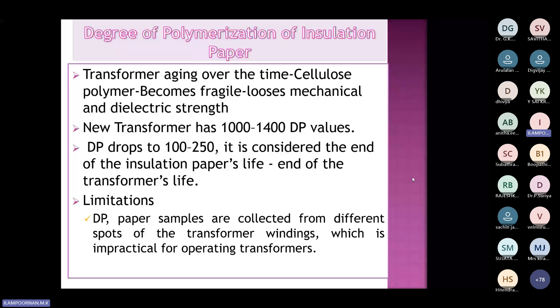That is the worst case, and it won't happen for 100 years - maybe another 100 or 200 years, we don't know. So if you want to test the insulation of the paper, you have to take a sample of it. But how? You'd have to open the transformer and take the paper out, which is not practically feasible. So even though this looks like a promising technique to understand insulation strength, it's not a practically viable option. I'm just mentioning it as one option, but it's not feasible.